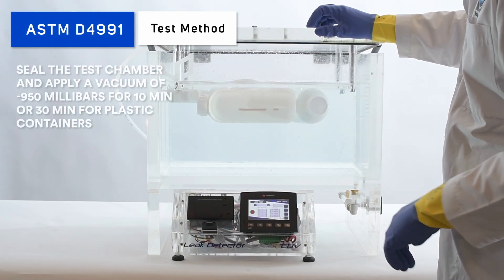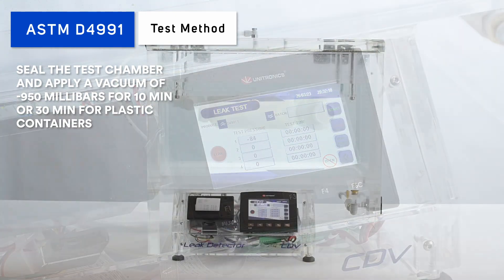Then seal the test chamber and apply a vacuum of minus 950 millibars for at least 10 minutes or 30 minutes for plastic materials.